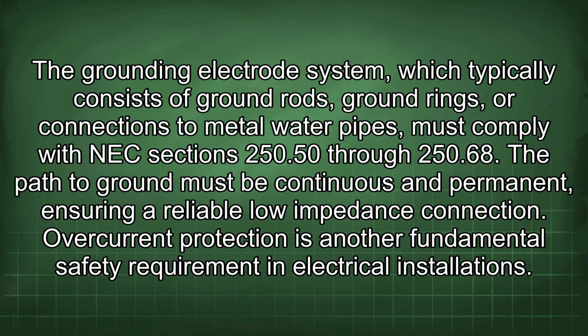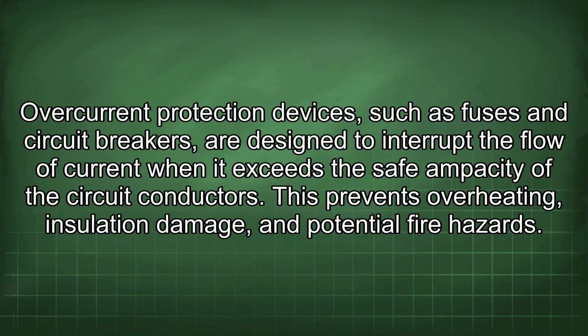Overcurrent protection is another fundamental safety requirement in electrical installations. Overcurrent protection devices, such as fuses and circuit breakers, are designed to interrupt the flow of current when it exceeds the safe ampacity of the circuit conductors. This prevents overheating, insulation damage, and potential fire hazards.